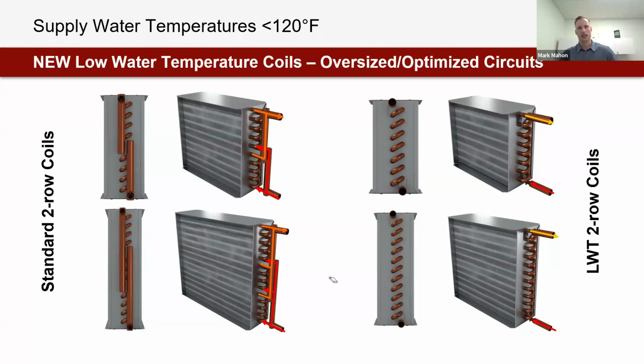And I'll give my pitch on circuits, which I think is maybe some additive context. So when we look at a circuit, it's an individual path for fluid to flow through the coil. What we're going to see circuits having most influence on historically, for most products, so a fan coil or a custom coil, why are we going to want more circuits? We're going to want more circuits because we want more fluid through the coil. Every tube has a maximum tube side velocity that we can actually push fluid through those tubes. And what we'll see for heating is about 5 feet per second is about the maximum tube velocity that we can reasonably push through an individual tube. So that equates to about 3.8 GPM per circuit.